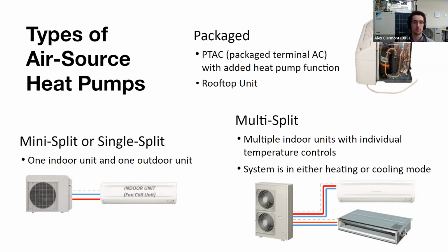Mini splits or multi splits are like residential or commercial versions of air source heat pumps. A mini split is where you have a single indoor unit tied to one condenser, and a multi split is where you have multiple indoor units tied to a condenser or an outdoor unit, as it's not always a condenser. With a multi-split, each zone or each indoor unit will have its own control, but the entire system will have to be in heating or cooling.